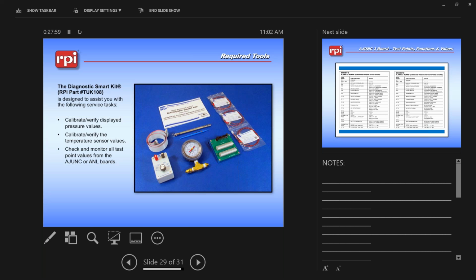And what you're going to be looking for is negative 5.1 millivolts. It's important that you know that your meter is reading millivolts and not volts. This is also a very tricky calibration setup because that negative 5.1 is a trigger for one of the chips that's on the board. So getting to negative 5.1 and having it hold there may be a little complicated. So if you end up at 5 or 5.2, that's fine.